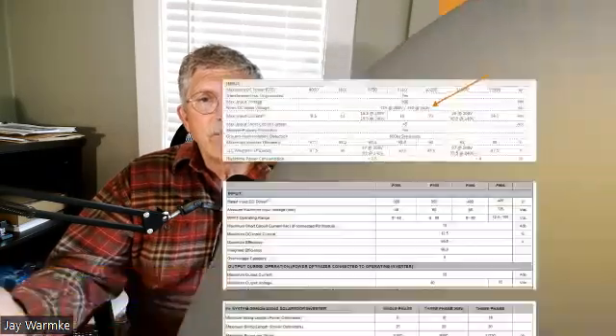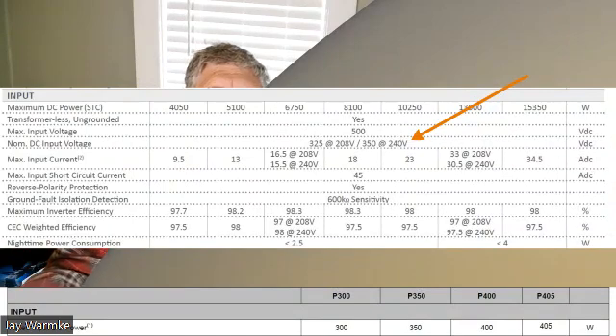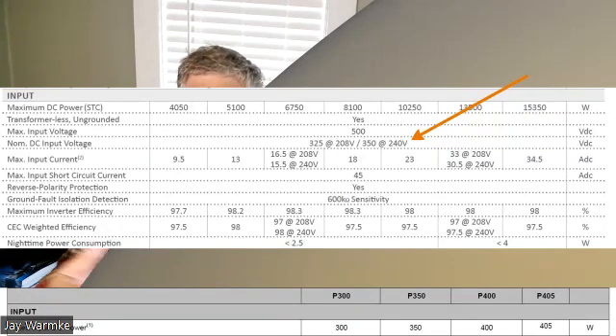Okay, so that's important to bear in mind when we're talking about SolarEdge or Enphase systems. Now, SolarEdge is another example, because these are really the two that are out there in the field. The input range from the fixed voltage inverter, as far as I'm reading this, looks to me like it's 350 volts. That's its nominal DC input voltage. That was a little confusing to me because all the literature I ever read on SolarEdge always mentions 400 volts as its operating voltage, but this spec sheet is telling me 350. So that's what I'll go with. So when it reaches the inverter, the voltage has to be at 350.